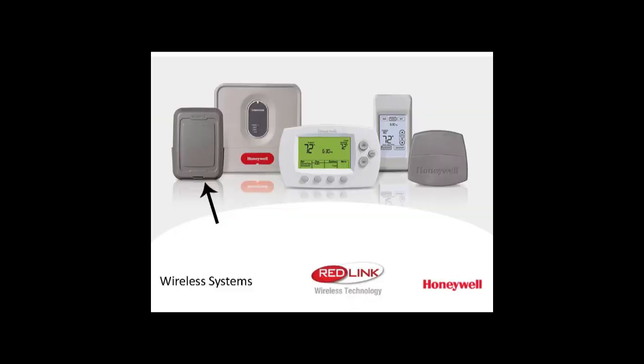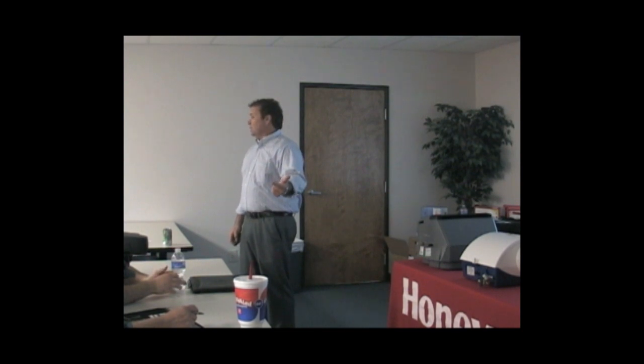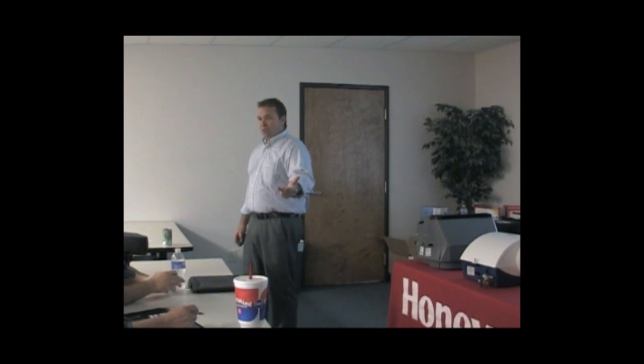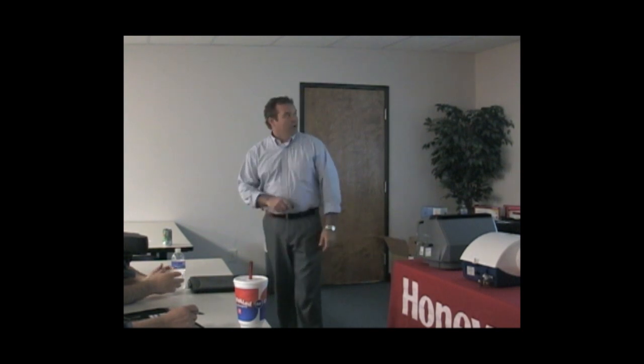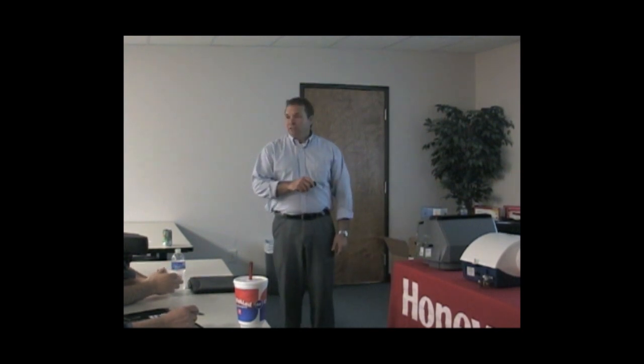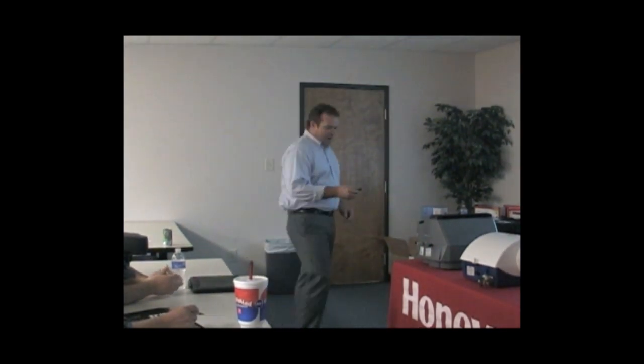So this nice little doohickey here, that's our wireless outdoor sensor. Lithium batteries last for 5 years. With lithium batteries, you can't put alkalines in it because it gets very hot and very cold here - alkaline lasts about 2 weeks in that system, lithium lasts a good 5 years. You'll get a flashing light that says it's 2 months away, change me, and they should be changing the batteries. You should be doing it on a service call or maintenance call anyway. So that's a bit of a revisit on what those are.